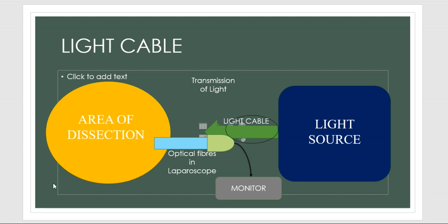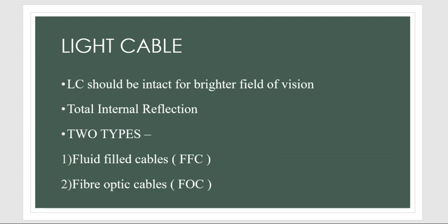In this video we are discussing the light cable. We must remember that the light cable should be intact in any surgery if we want a brighter field of vision. The basic principle on which it functions is the total internal reflection of light. Based on this theory, light cables are basically of two types: the fluid-filled cables, known as FFC, and the fiber optic cable.